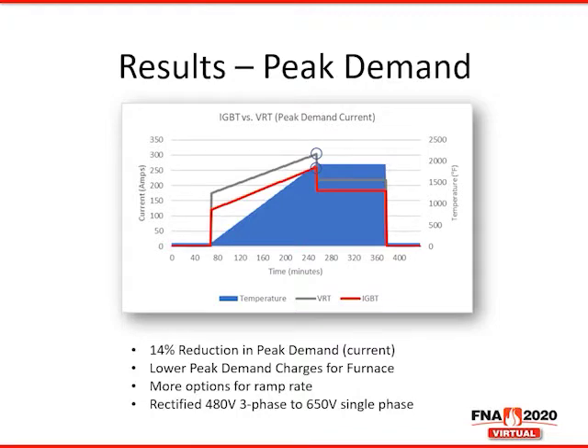Next, let's look at the peak demand, or the most amount of current that's used for the process. This graph is similar to the last slide, where you have the heat treat cycle in blue and a plateau up to 1900 degrees, but our left y-axis now is amps, or current. And again, you can see the trend of increasing current during the ramp phase and then a plateau phase. In the circles in the graph, you can see our peak current draw. And we identified a 14% reduction from the VRT to the IGBT MFDC power supply.